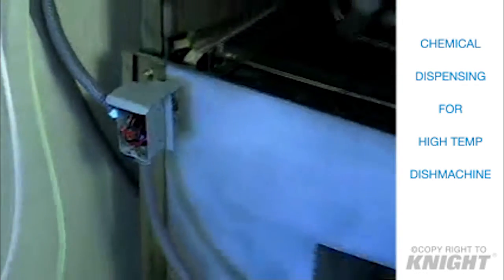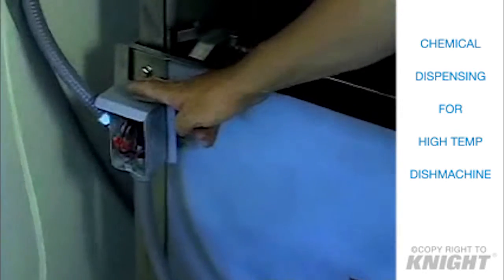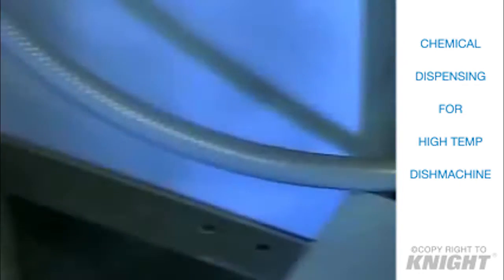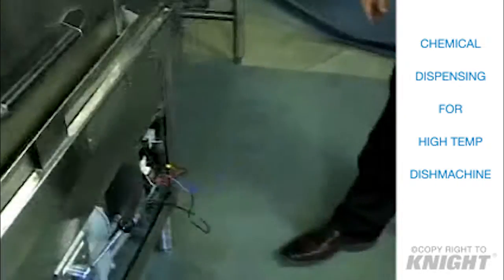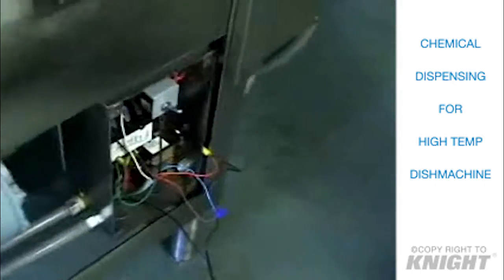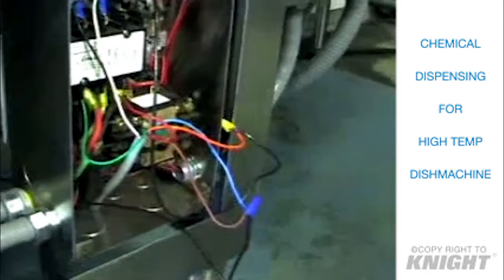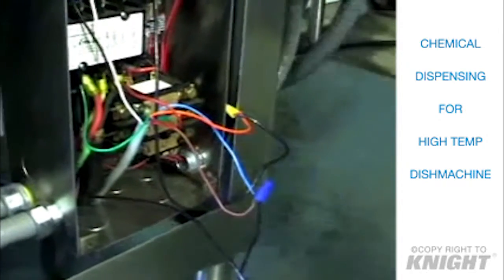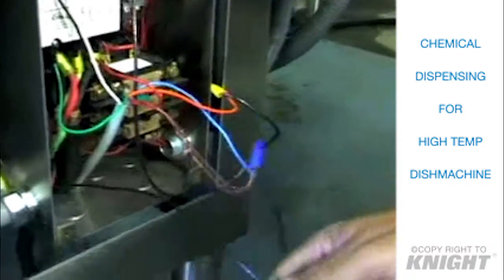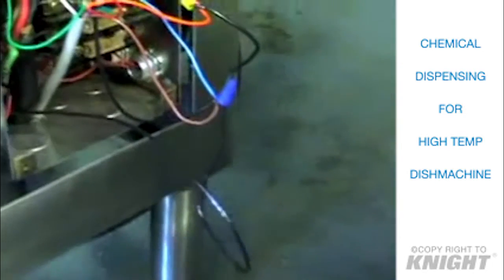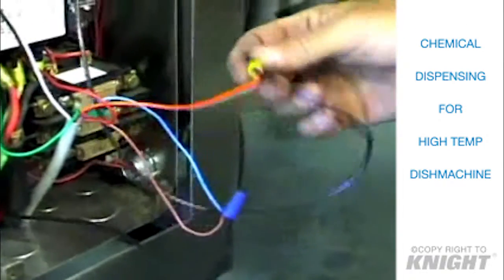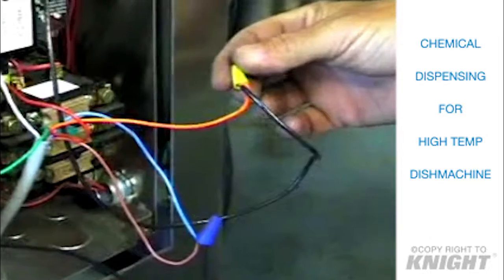What we've done is I've run an extra line from the secondary side of the switch that's in here, and I've run it through this conduit and back into the power supply box. Now you can do it that way if it's convenient for you, or you could run another piece of conduit and bring it into the power supply box, but this is the wire that I ran right here. And then you can see this wire is the other side of my rinse signal.